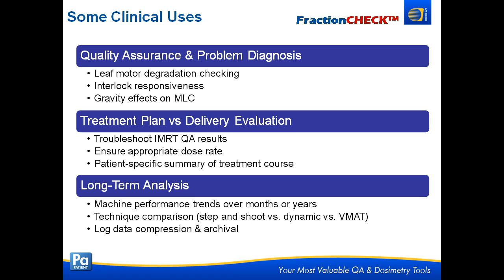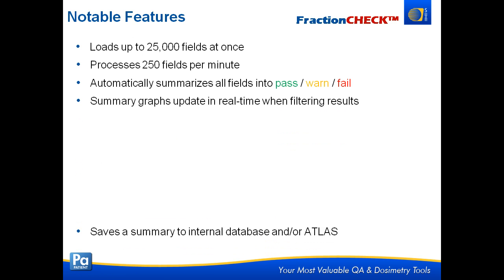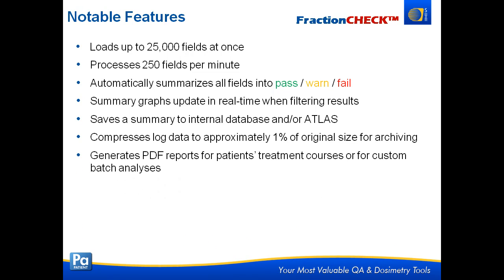For long-term analysis, physicists who would like to see how their machines performed over months or years — FractionCheck can handle around 25,000 files. You can compare different techniques: VMAT, dynamic, step and shoot. You can compress your log data for archiving purposes. Some statistics: we can load 25,000 fields at one time, process about 250 fields a minute — a very fast analysis designed to handle thousands and thousands of fields at once. Everything is summarized into pass, warn, or failed results. We generate graphs that update in real-time when you sort and filter results, save a summary to the internal database or Atlas. Compressing log data results in files that are about 1% of the original size, so you don't have to throw away those Dynalog files. We generate PDF reports for patient treatment courses or custom analyses.